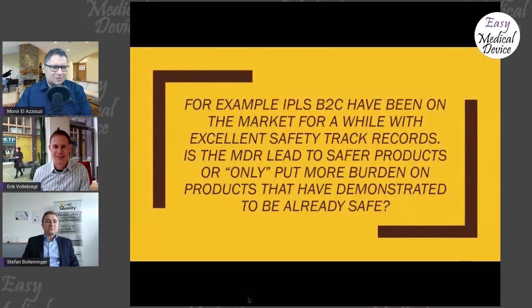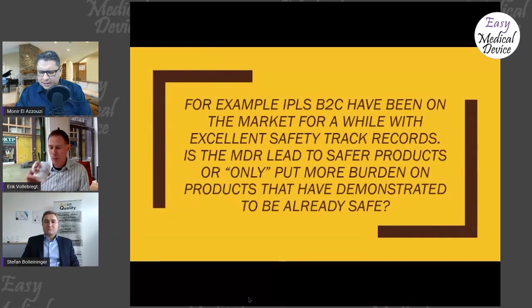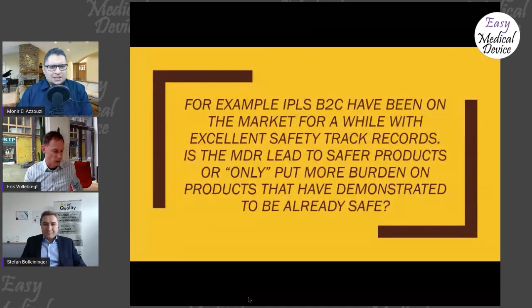Yeah, no, I think, as you said, the double side. So just one thing, I have a comment here from Keith Wilkinson. Is there a level set for the amount of energy being transferred to the body, which means that a product is covered by the MDD, such as EMS? But here, a non-medical device is not covered by the MDD, so it's mainly for the MDR only. But is there a limit where we say that this amount of energy means that we have a transfer to the body, or is anything that is transferred to the body as energy considered an active device?